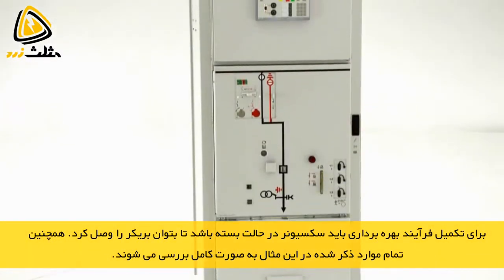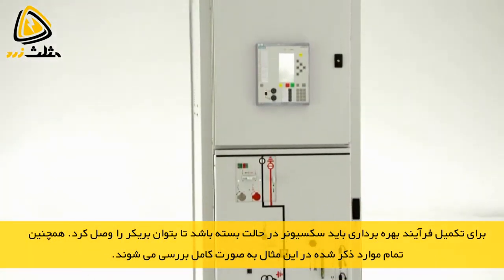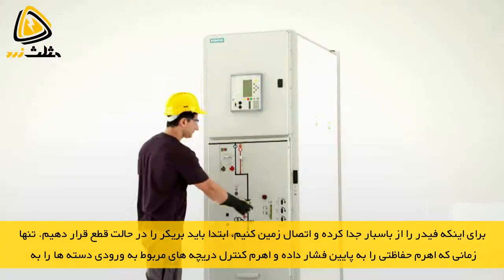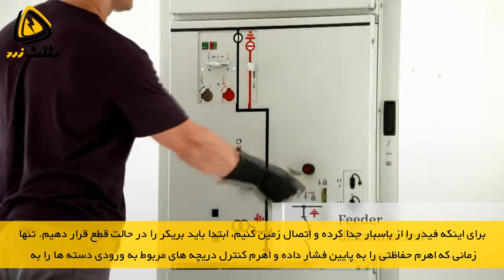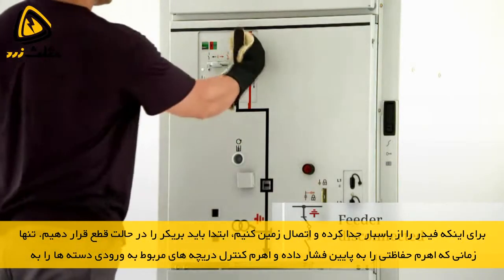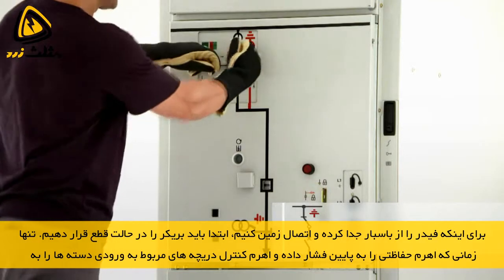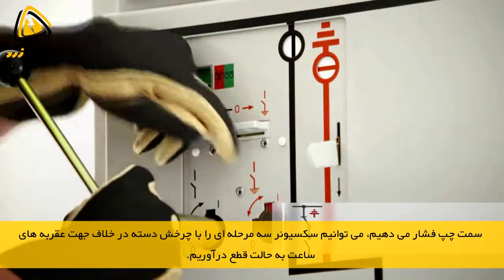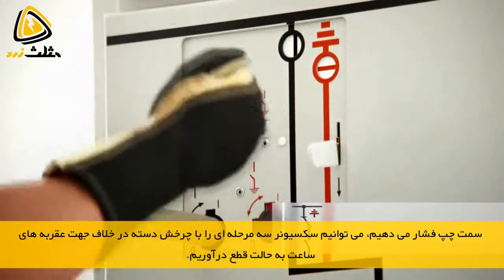We'd like to show you this principle in more detail using NX Plus C as an example. To disconnect a feeder from the bus bar and to earth it subsequently, the circuit breaker is first switched to the open position. Only after the interlocking lever has been pushed down and the control gate has been pushed to the left, can the three-position disconnector be switched to the open position by turning the operating lever counterclockwise.